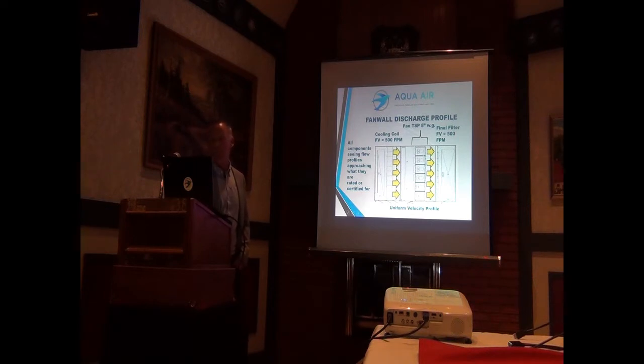Why is it important with the direct drive motors? You don't have belts, you don't have belt losses and drive losses. So that also improves your efficiency. As you can see here, we're talking about the final filters. These arrows are indicating the profile of the air you're going to utilize, near 100% of the filters' square area that you designed the unit for.